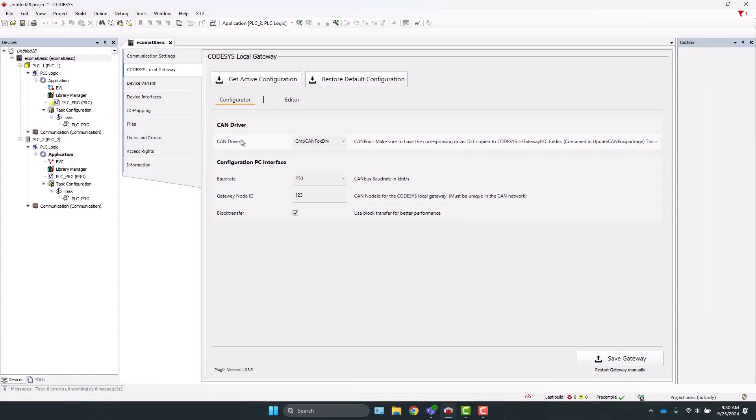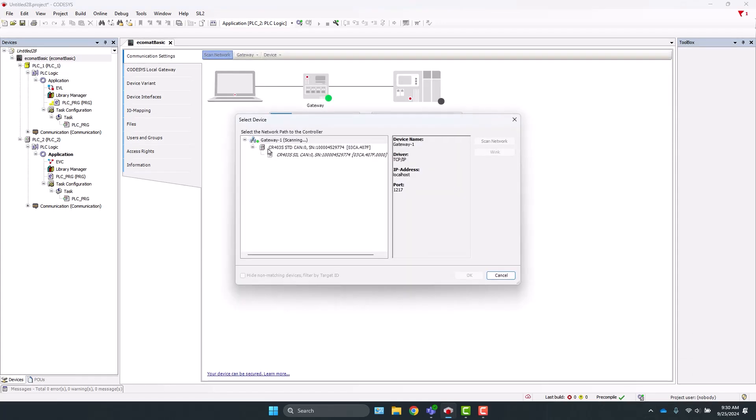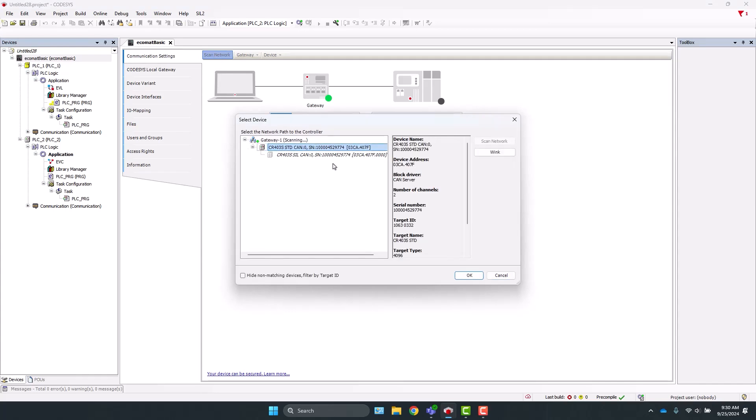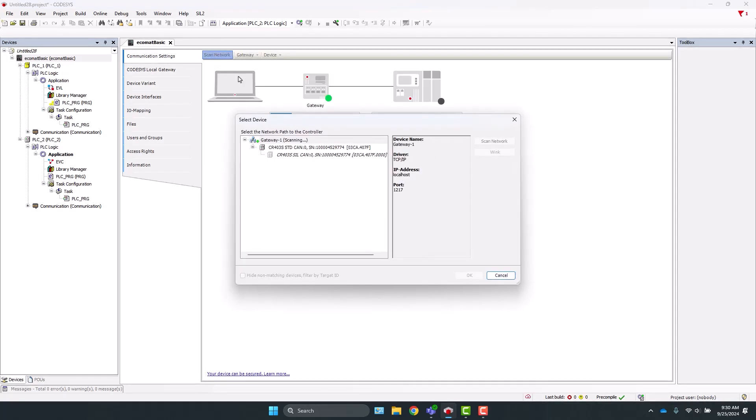So at this point, we'll come back to communication settings and click Scan Network. And now we see the CR403S, and we can select that from the tree. Note that if you scan after you change the gateway and it does not work, you may need to reboot your PC for the settings to take place.